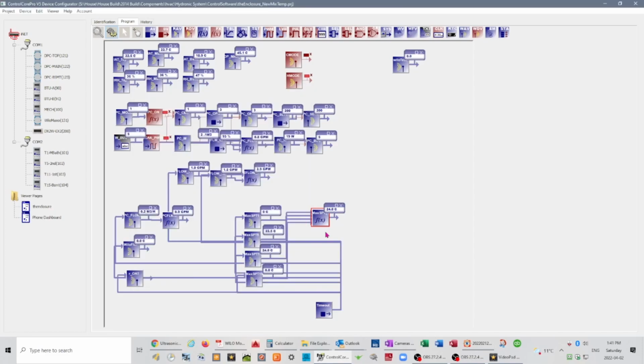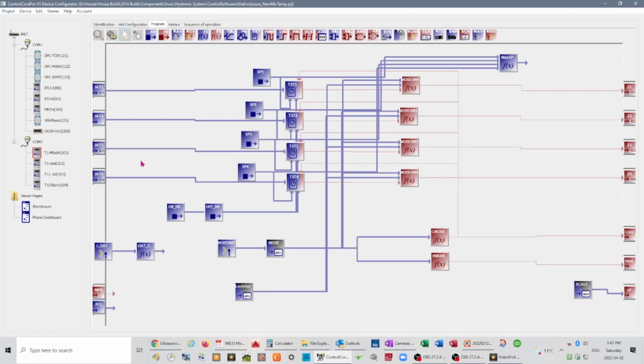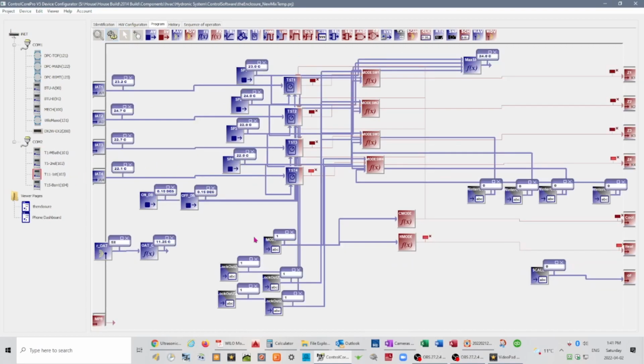So I'm setting the max based on all of these blocks that I'm calling remotely from the 4 thermostats. And in those thermostats, the T-stats, I am creating the maximum set point based on all of these set points. So these are set points that you can do at the code level, or you can go to the physical device, scroll through to the zone you're after, zone 1, 2, 3, 4, and the matching actuators, and set the set points on the device themselves.